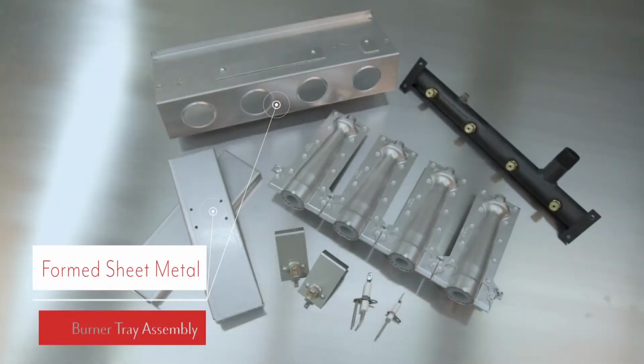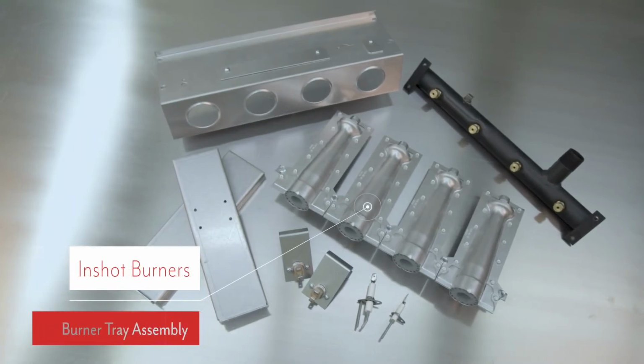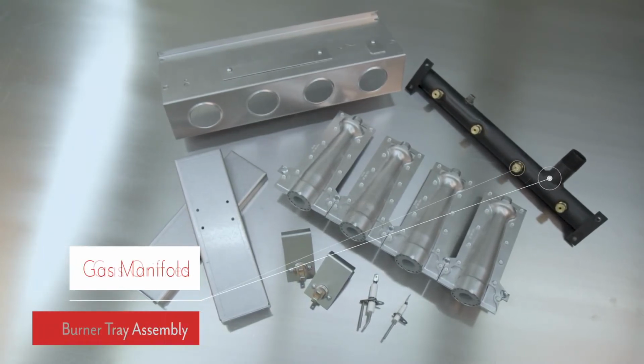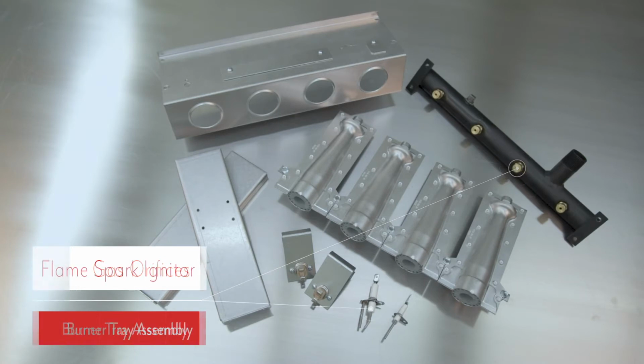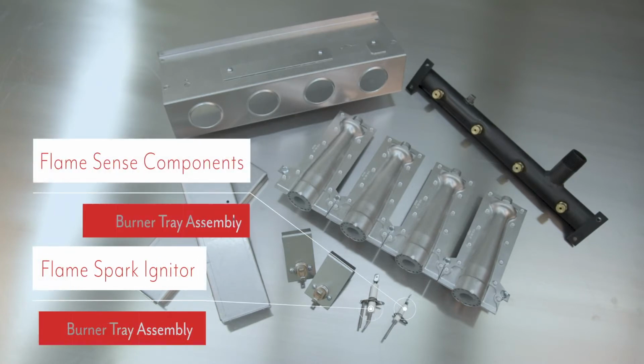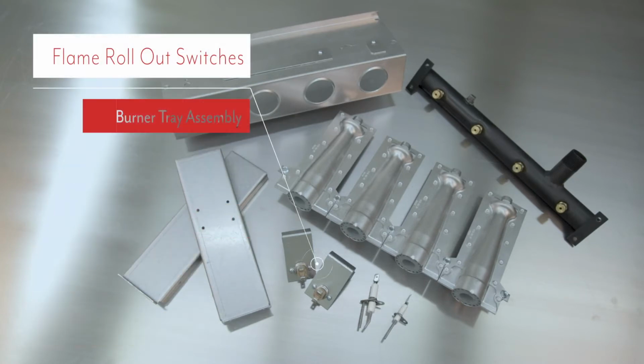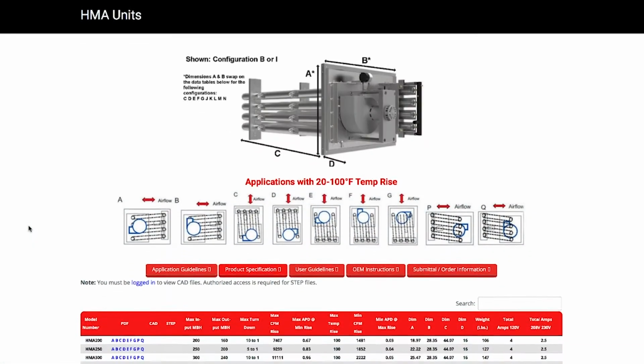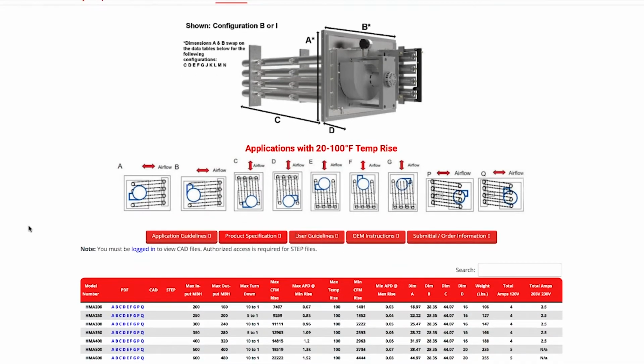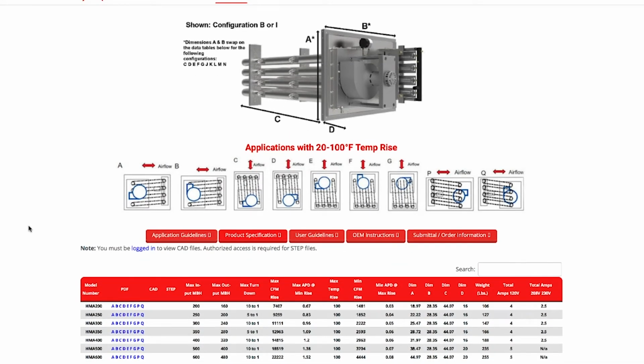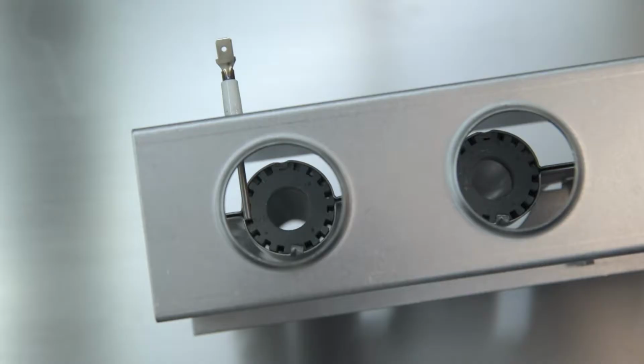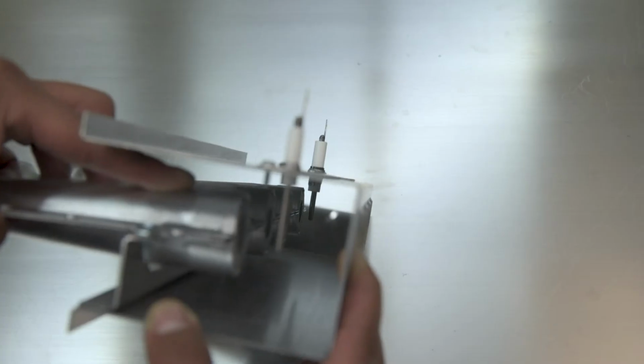Burner tray assemblies consist of formed sheet metal, in-shot burners, gas manifold, gas orifices, flame spark igniters, flame sense components, and manual reset flame rollout cutoff switches. The construction of the burner tray is based on input, orientation, and specified furnace control. The burner tray locates the spark igniters and flame sense components. These locations are very specific.